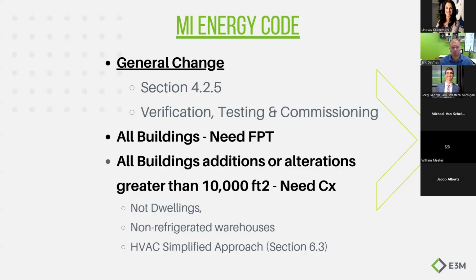Another exemption to the commissioning requirement is a non-refrigerated warehouse—to be clear, not a manufacturing facility. If it's a manufacturing process that's heated and cooled, that requires commissioning. But a storage warehouse that's not refrigerated is exempt. There are other small exemptions by section, but be aware that this is the biggest change in this code and has the most impact.